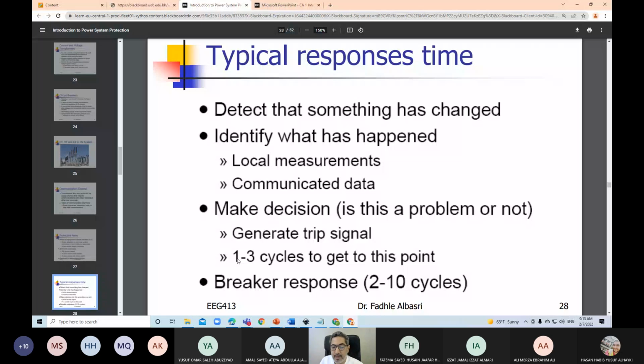And this circuit breaker is a mechanical device. It takes time to open its contacts. So it sometimes takes 2 to 10 cycles, depending on the type of the circuit breaker. Now, what are the detection principles? How do we detect that there is a fault or that this is a normal condition? There are different detection criteria.